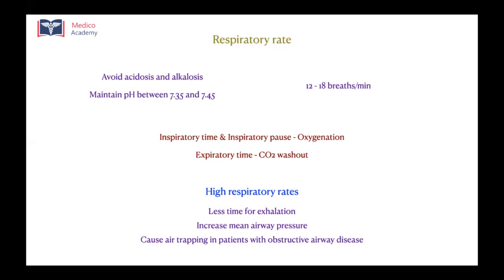So usually in ventilators, you can decide the inspiratory time and respiratory rate. So when you manipulate the respiratory rate, it happens at the expense of expiratory time because you have already set the inspiratory time. It remains constant. So if you increase the respiratory rate, you will see that the expiratory time gets shortened. As the expiratory time gets shortened and air trapping occurs inside the patient, you have less time for exhalation. That can slowly increase the mean airway pressure further, which will result in barotrauma. So you need to be very careful when you're increasing the respiratory rate of the patient. We'll repeat this important point again in the next few slides.